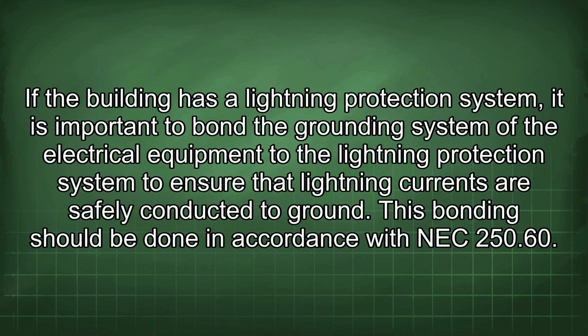If the building has a lightning protection system, it is important to bond the grounding system of the electrical equipment to the lightning protection system to ensure that lightning currents are safely conducted to ground. This bonding should be done in accordance with NEC 250.60.